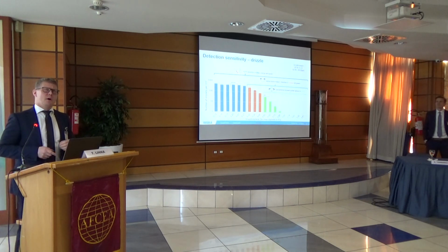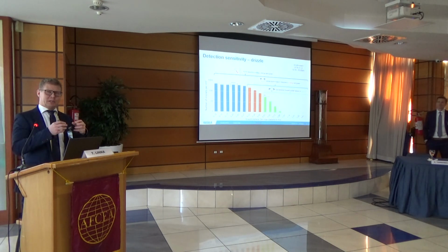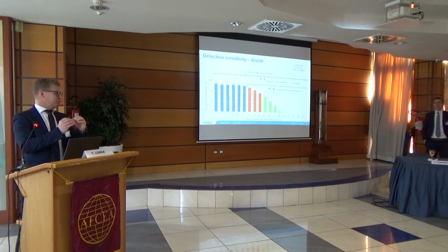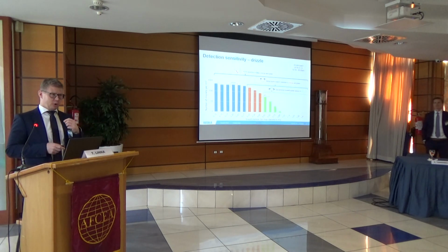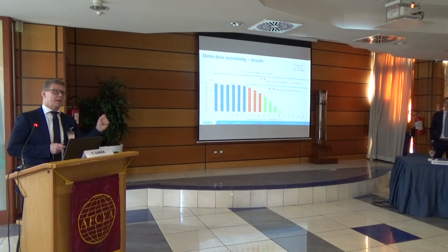the fog. Yeah, we can't promise any forward scatter sensor with forward scatter technology cannot be more accurate than 10% of uncertainty in low visibility conditions. It's the limitation of the technology. So in real conditions, we will achieve 10% plus minus, and we promise that one. But we couldn't promise like 5% because it's physically impossible. That's why I always promote the transmissometer to those conditions where one wants to achieve plus minus 1% or less.